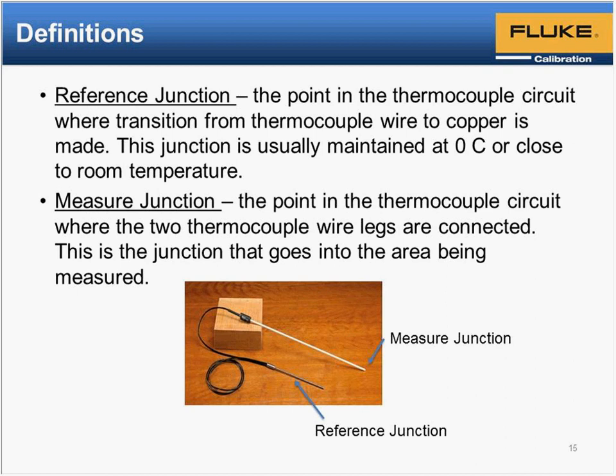Next question is, how often should we check for inhomogeneity? That's a good question. I've contemplated having a separate webinar just about homogeneity, because it's a topic for laboratories that are calibrating thermocouples. For example, we have to do an inhomogeneity test when we rate type S, type R thermocouples. It's required for any accredited laboratory. But there's a lot of controversy out there about how to measure inhomogeneity, and even if you go out and buy the world's best wire scanner, people can't say for sure what the uncertainty from inhomogeneity is, but they make attempts to calculate it.